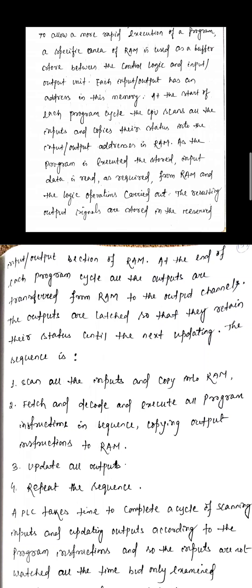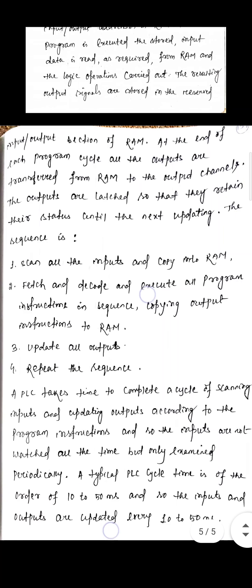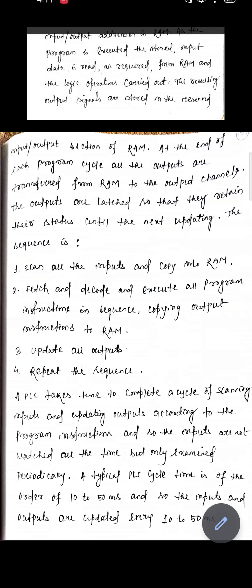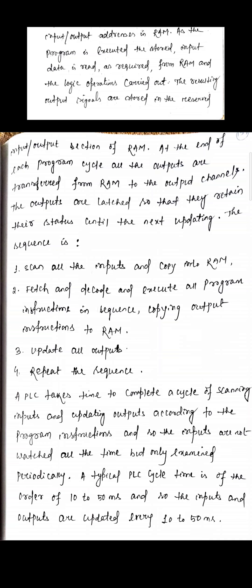A PLC takes time to complete a cycle of scanning inputs and updating outputs according to the program instructions. The inputs are not watched all the time but only examined periodically. A typical PLC cycle time is of the order of 10 to 50 milliseconds, so the inputs and outputs are updated every 10 to 50 milliseconds.